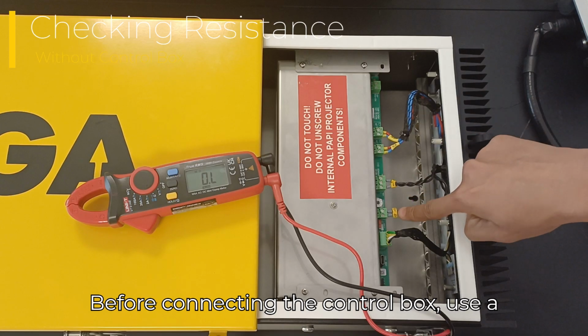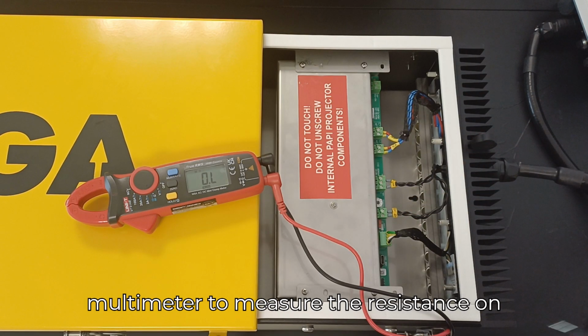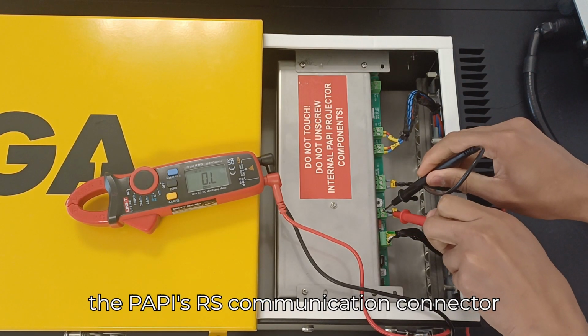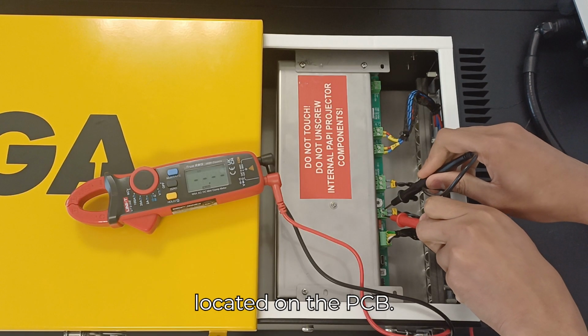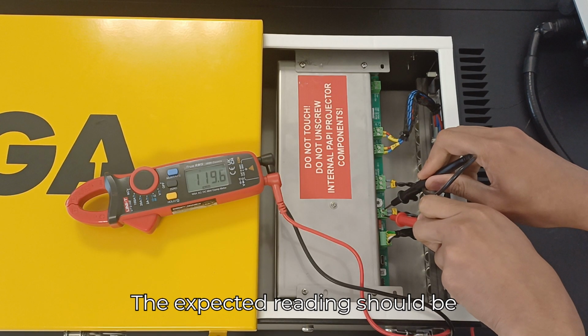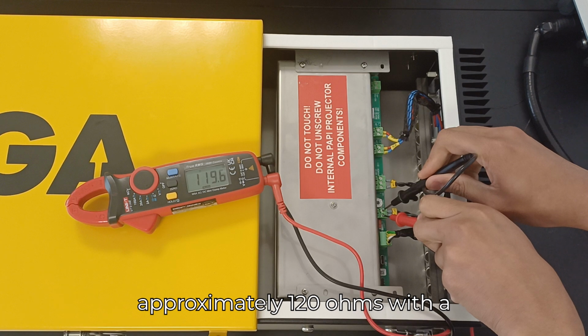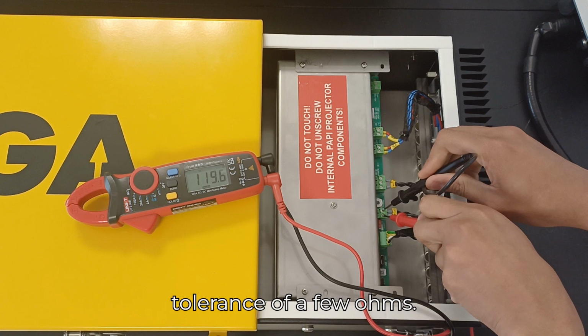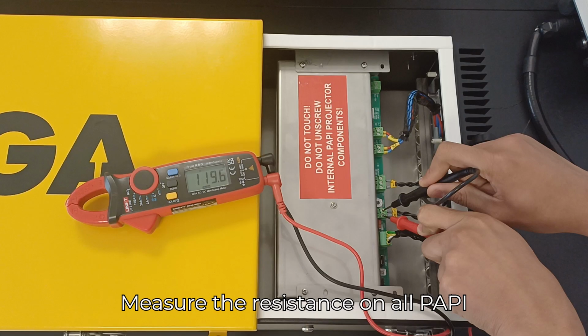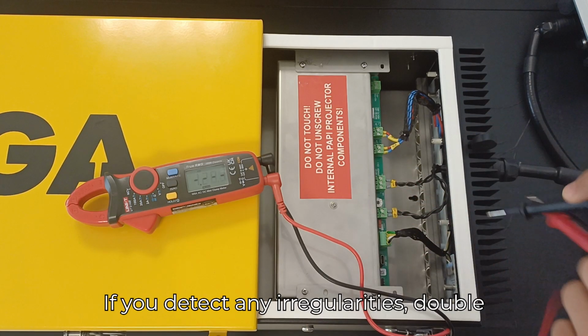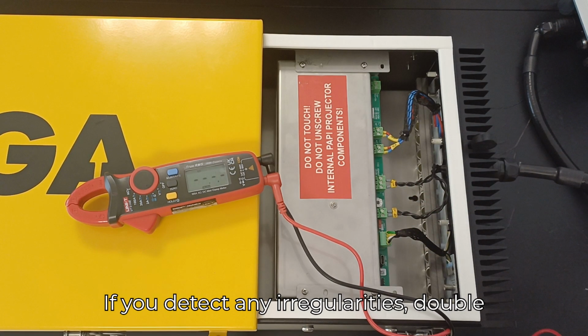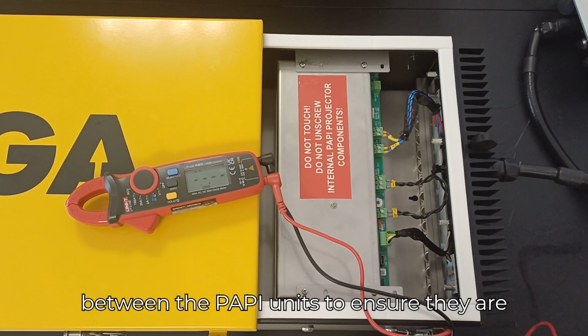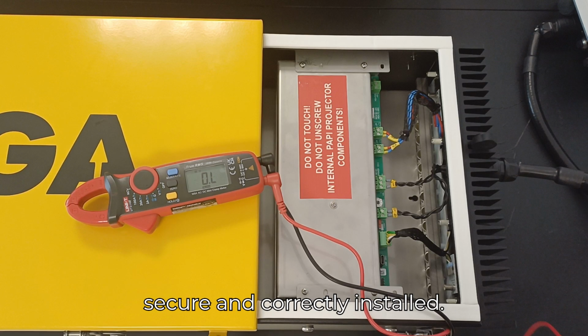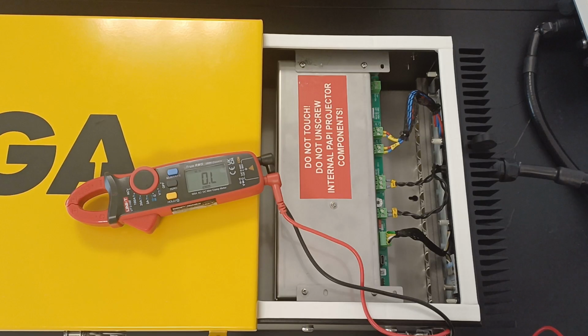Before connecting the control box, use a multimeter to measure the resistance on the PAPI's RS communication connector located on the PCB. The expected reading should be approximately 120 ohms, with a tolerance of a few ohms. Measure the resistance on all PAPI PCBs. If you detect any irregularities, double-check the communication cable connections between the PAPI units to ensure they are secure and correctly installed.